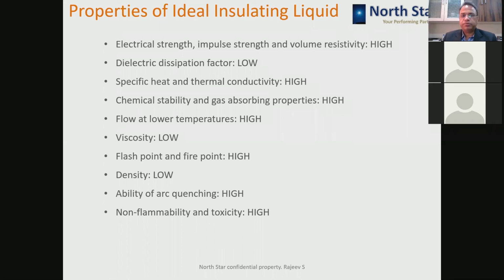That means the viscosity should be low, and it should have a higher flash and fire point because there is arcing and over temperature inside, and the paper is there, so it shouldn't be conducive to the starting and continuity of fire. It should have low density, and it should have high arc quenching capability. It shouldn't be flammable, and it should not be toxic. So it should be neutral from that purpose. So an ideal insulating liquid should have these properties.